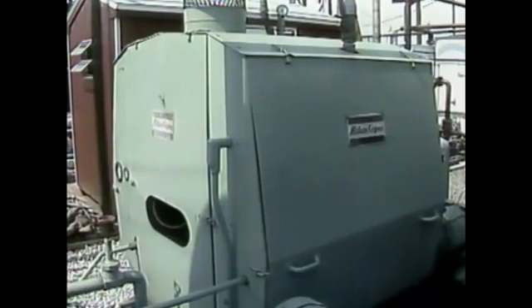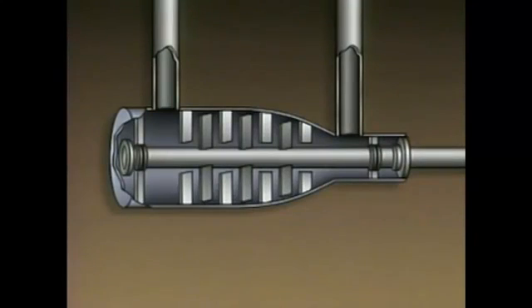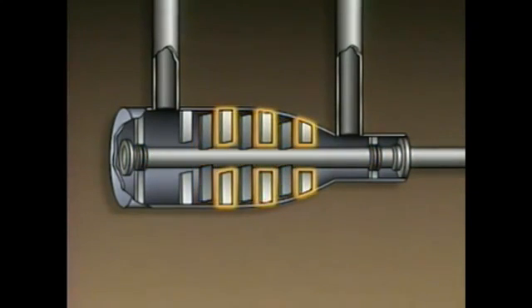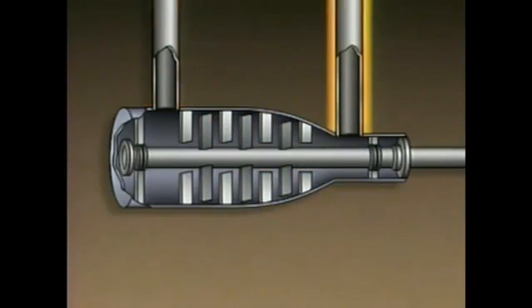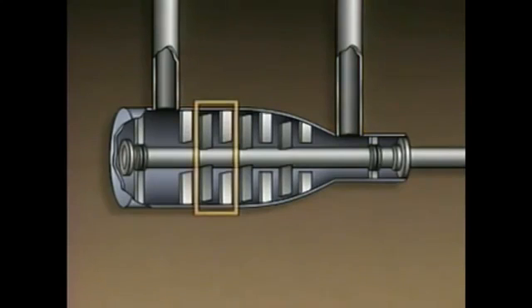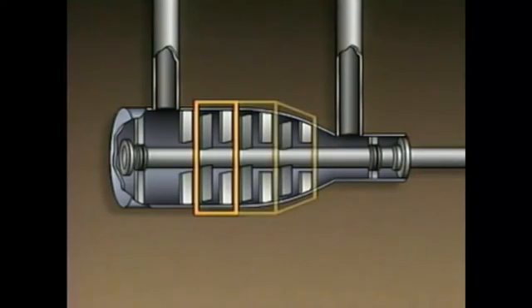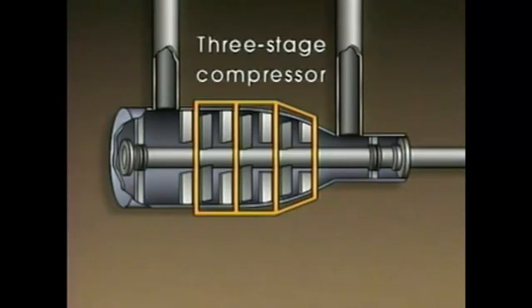As shown in this simplified illustration, an axial compressor's main parts typically include a shaft, bearings, seals, rotating blades, stationary blades, a suction line, and a discharge line. Each set of rotating blades followed by a set of stationary blades is called a stage. This compressor has three sets of rotating and stationary blades, so it can be called a three-stage compressor.